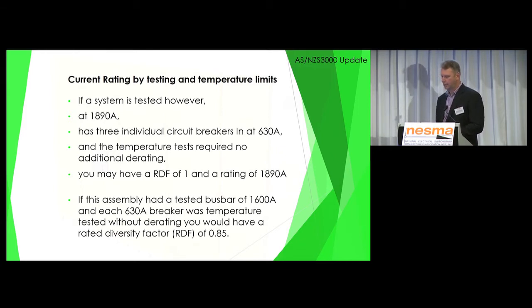If this assembly had a tested bus bar at 1600 amps, but we had no further derating for temperature of the circuit breakers, then your rated diversity would be 0.85. So I hope that's not confusing too much. We've got lots of derating factors involved, but essentially the first one to look at is the rating of the circuit breaker and how it's derated in its assembly, and then a further derating for diversity.